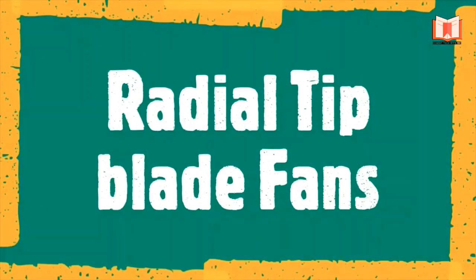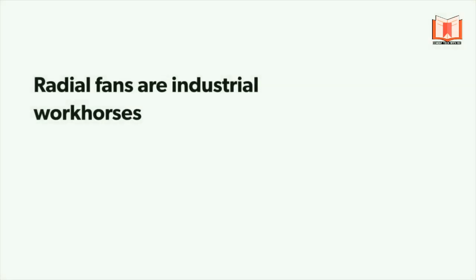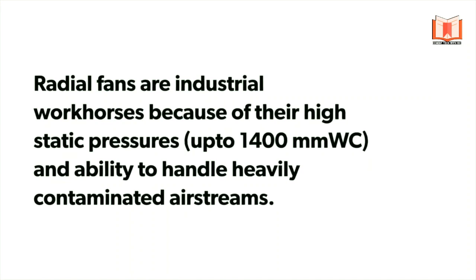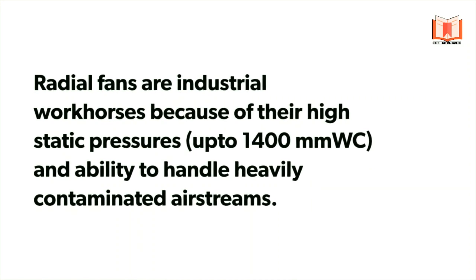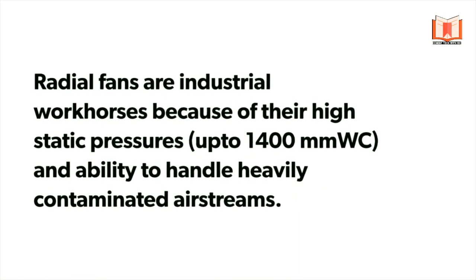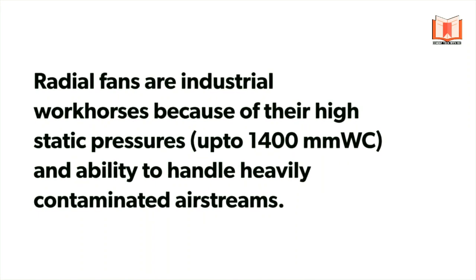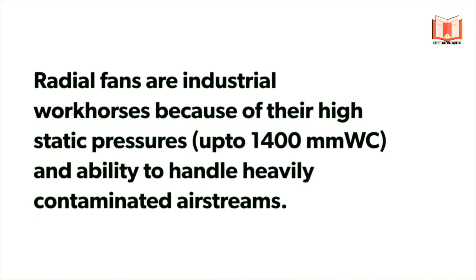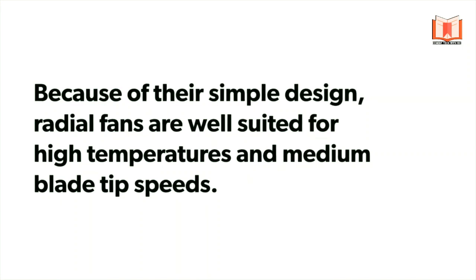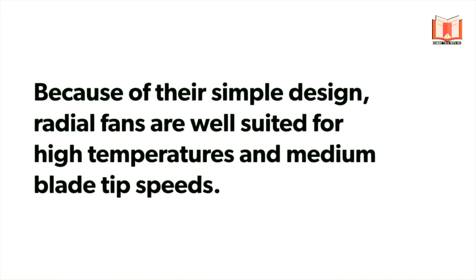Radial tip blade fans: Radial fans are industrial workhorses because of their high static pressure — up to 1400 mmWC — and ability to handle heavily contaminated air streams. Because of their simple design, radial fans are well suited for high temperatures and medium blade tip speed.